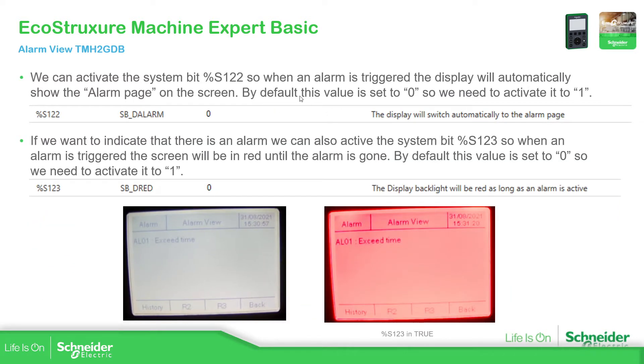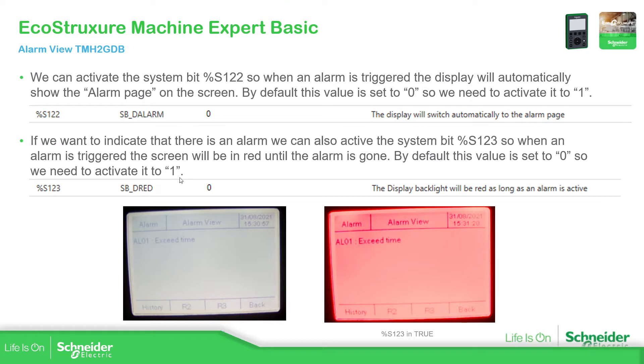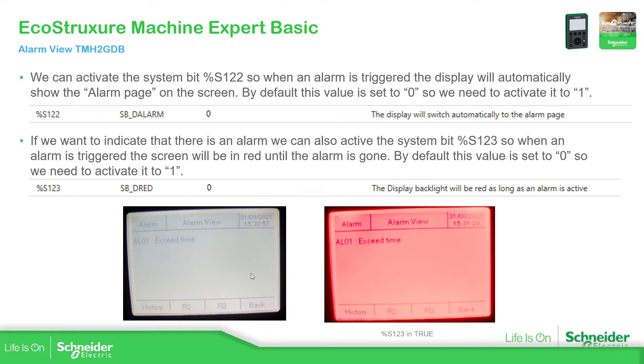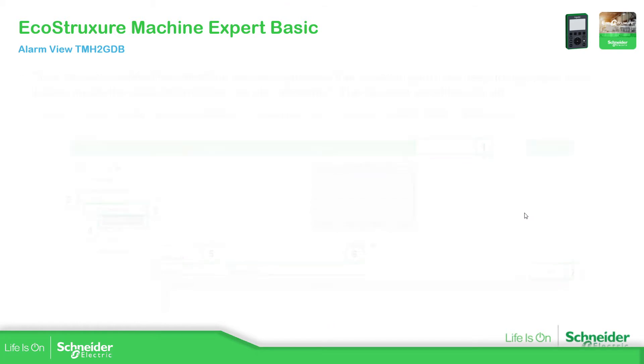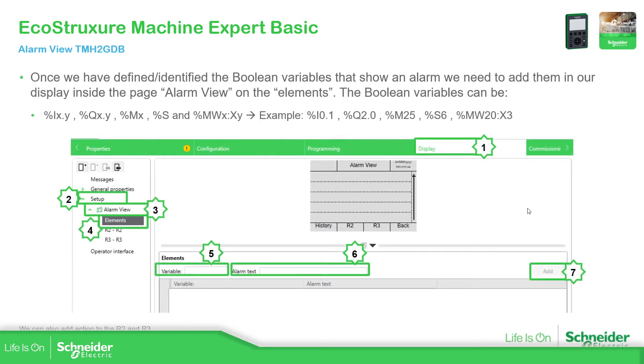And there are some important bits that we can use. For example, this bit, the %S123, by default is in zero, but if it's in true, when we have an alarm, it will show the display in red. And another important bit is the %S122, which allows you to directly go into the alarm view automatically without configuring something else.